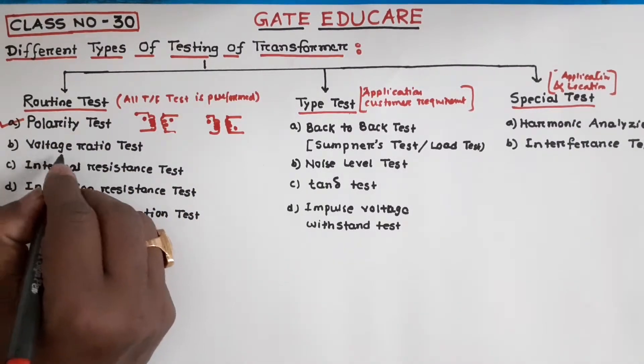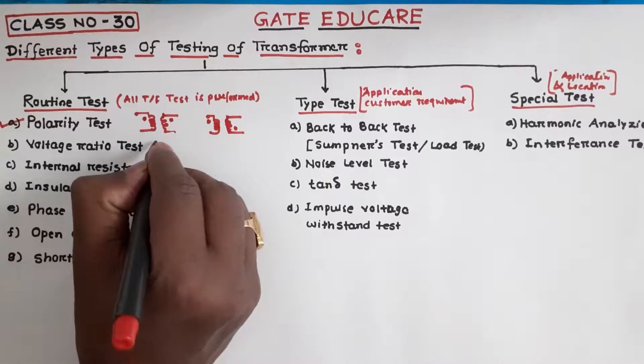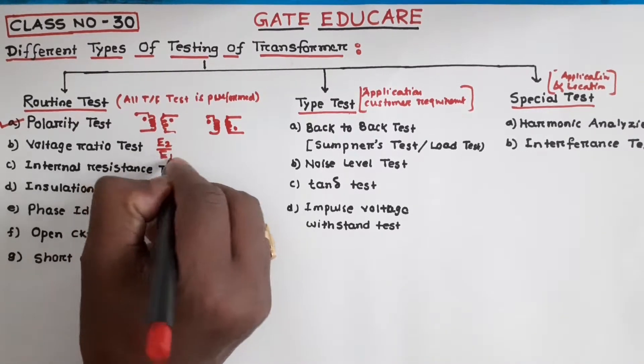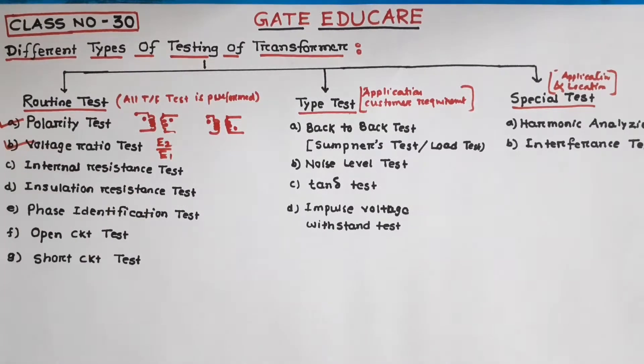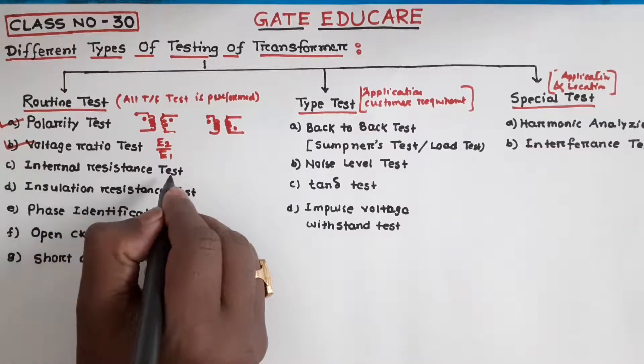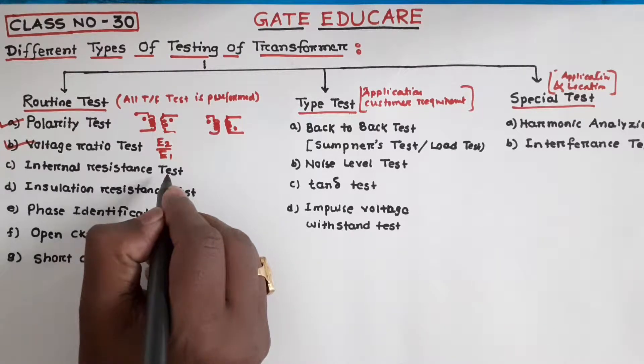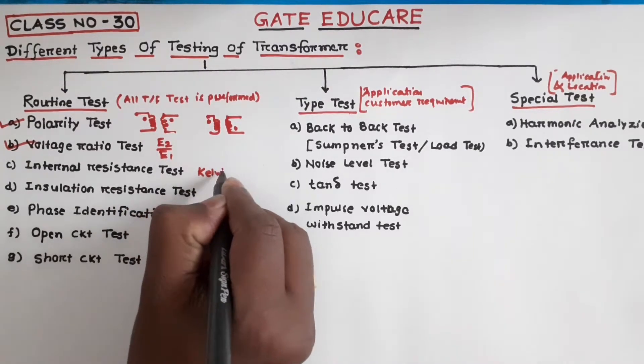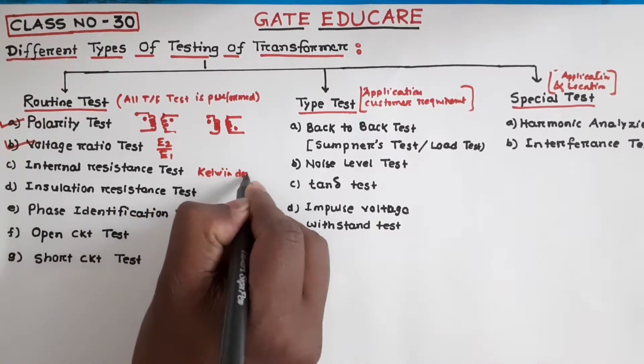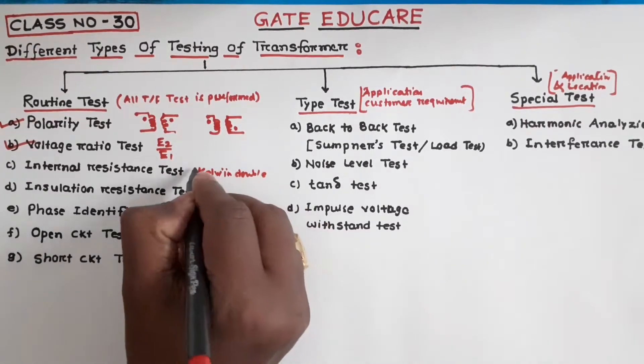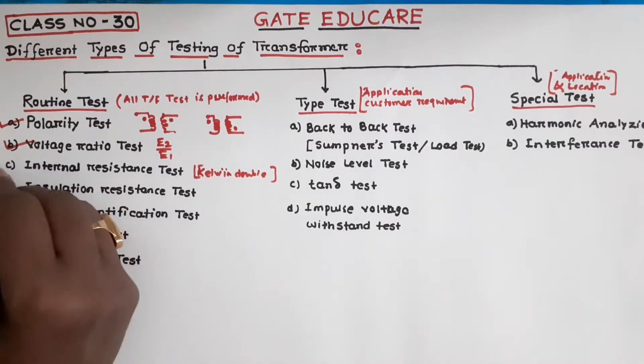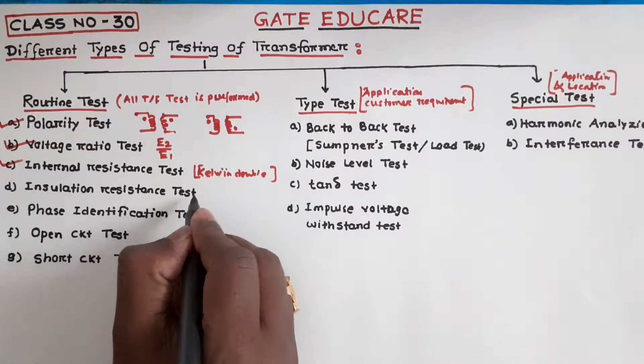Next, the voltage ratio test. With the help of the voltage ratio test, the voltage ratio E2 by E1 is determined. Internal resistance test: with the help of this test, the internal resistance of the winding is measured. Generally, the Kelvin double bridge is used to measure the resistance of the winding.